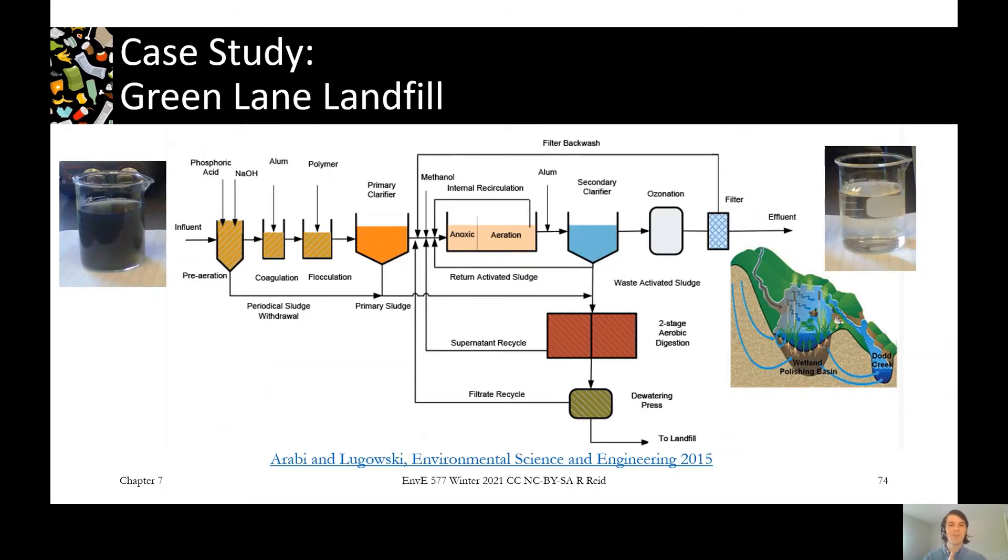I'll give you an example of one plant. This plant happens to look very much like a domestic wastewater treatment system. This is the leachate treatment system used at Green Lane Landfill owned by the city of Toronto. So you can look at the process train here and it looks very similar to domestic wastewater treatment. A couple little differences. So coming in, we've got a pre-aeration because our liquid is probably going to be anaerobic coming in from the bottom of the landfill.